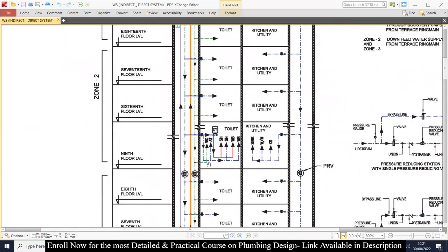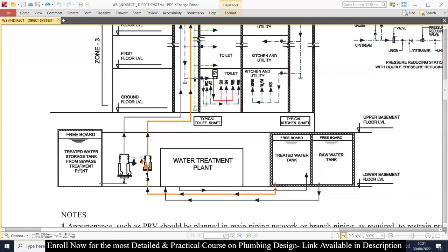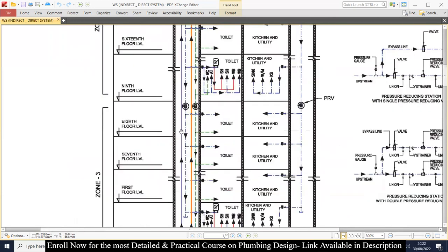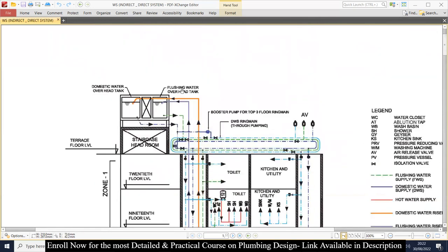The water from the gray water tank is supplied through the transfer pump directly to the roof level to the flushing water overhead tank. On the roof we have two types of tanks: one is the domestic water overhead tank and one is the flushing water overhead tank. The domestic water overhead tank supplies fixtures like lavatories, showers, and bathtubs, while the flushing water overhead tank supplies water to WCs and urinals.